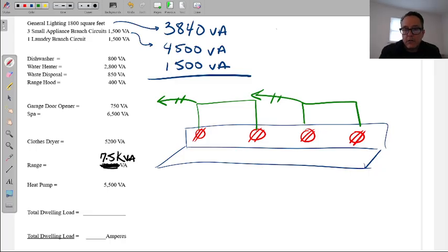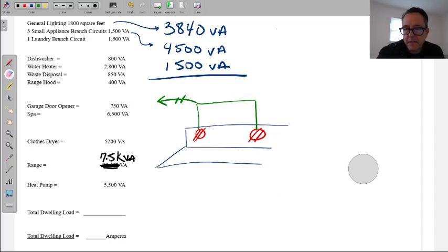If I've got a tiny countertop, then I might even have just 1 appliance load from the panel. I might have just 1 20 amp breaker because I don't have a lot of space. I only have this much as far as countertop goes. Little apartment. So I might just have 1 20 amp breaker servicing 2 outlets. But when the size of the panel was calculated, a minimum of 2 small appliance loads were calculated for that panel.